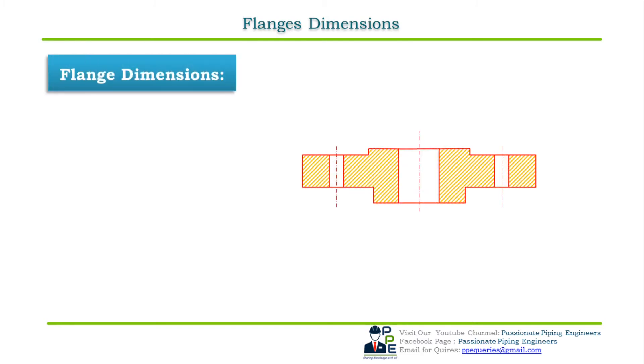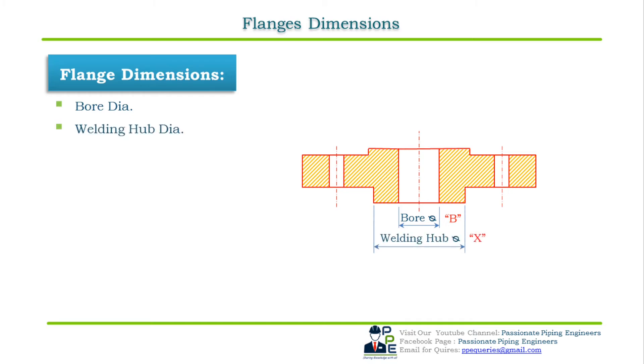Flange dimensions or flange nomenclature as per ASME B16.5 are as follows. Bore diameter is equal to the inside diameter of the pipe and usually depends upon the schedule of the pipe. Welding hub diameter is equal to the outside diameter of the pipe NPS. BCD or PCD — bolt circle diameter or pitch circle diameter — is the diameter of the circle which passes through the center of each bolt hole. It is one of the critical dimensions of the flange.